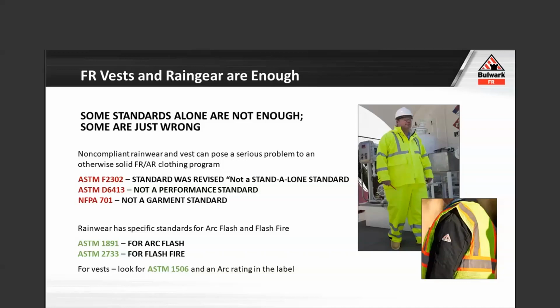Additionally, ASTM 6413, we see a lot, especially when it comes to high-vis 100% polyester vests that are marketed as FR. That is not a performance standard. That is the vertical flame standard. It is utilized for fabric evaluations all across our space, but as a standalone by itself gives you zero indication of how that will perform in an arc flash or a flash fire. If that's the only standard you can see in a label, you're jeopardizing your FR/AR clothing program, because this is now sitting on top of that, and it may nullify your whole investment in your shirts, pants, and coveralls by having the wrong vest. NFPA 701, thankfully, we don't see a lot of anymore.